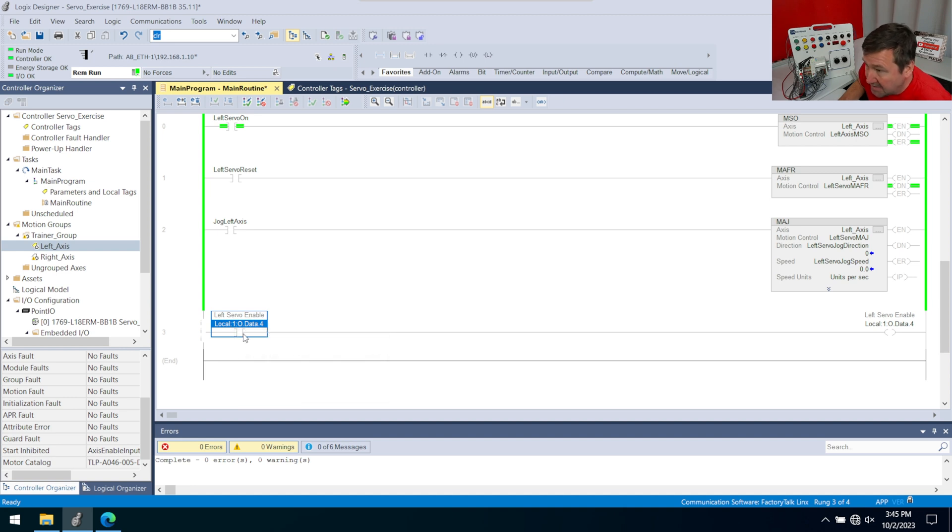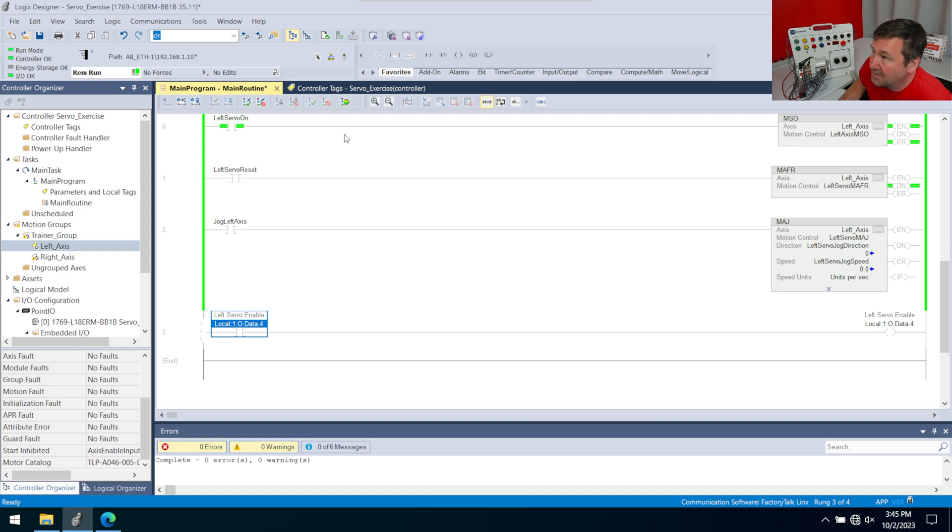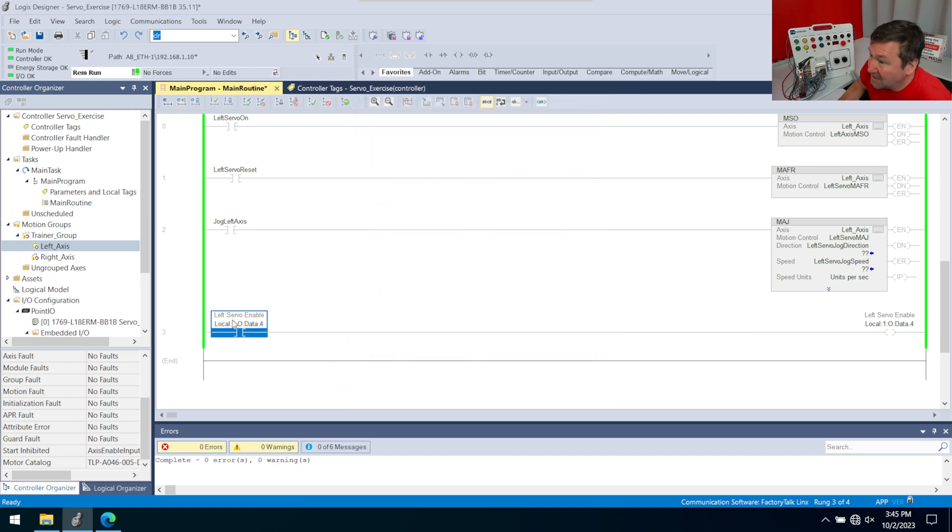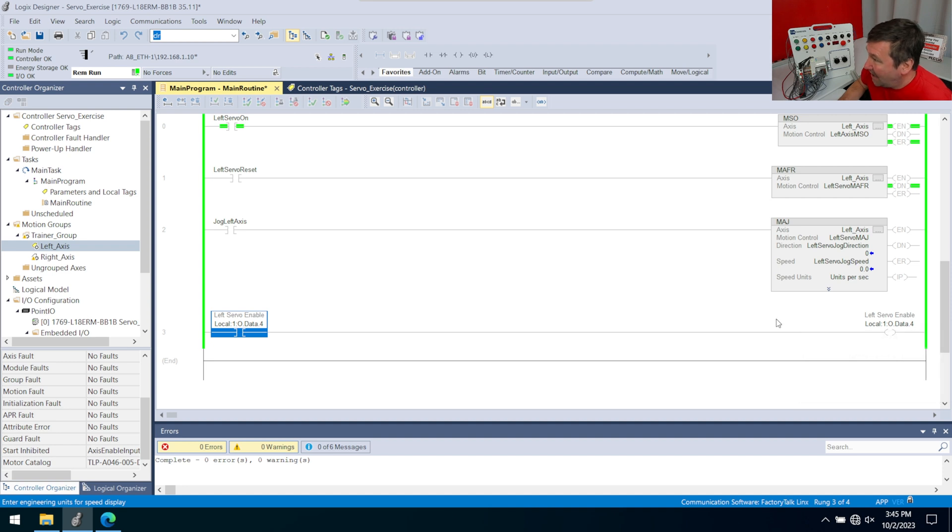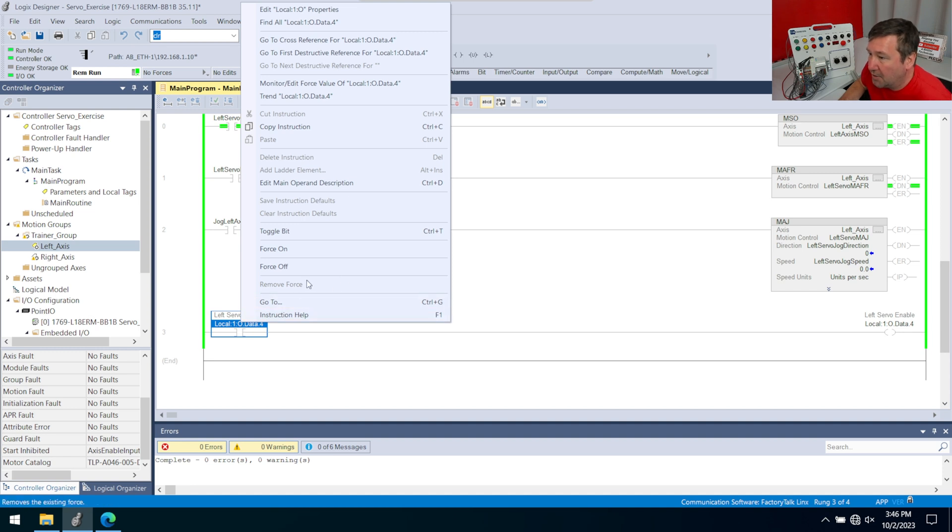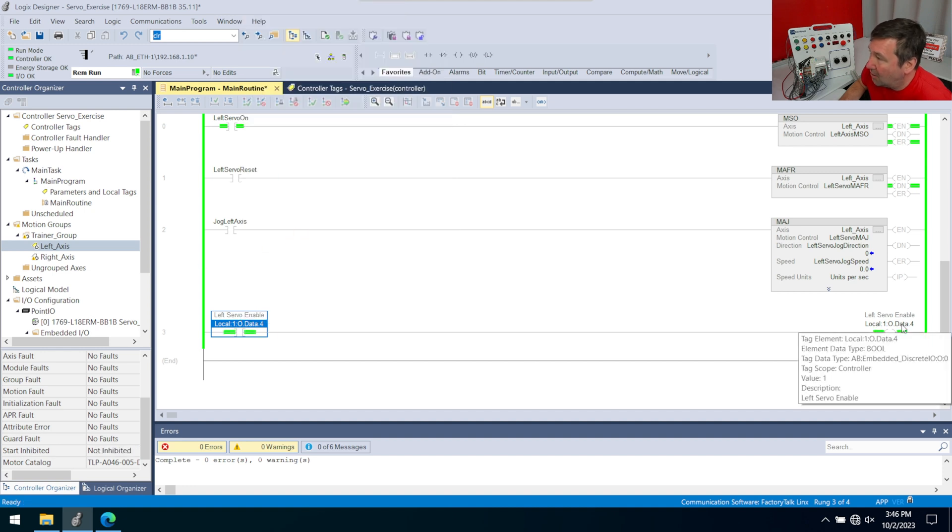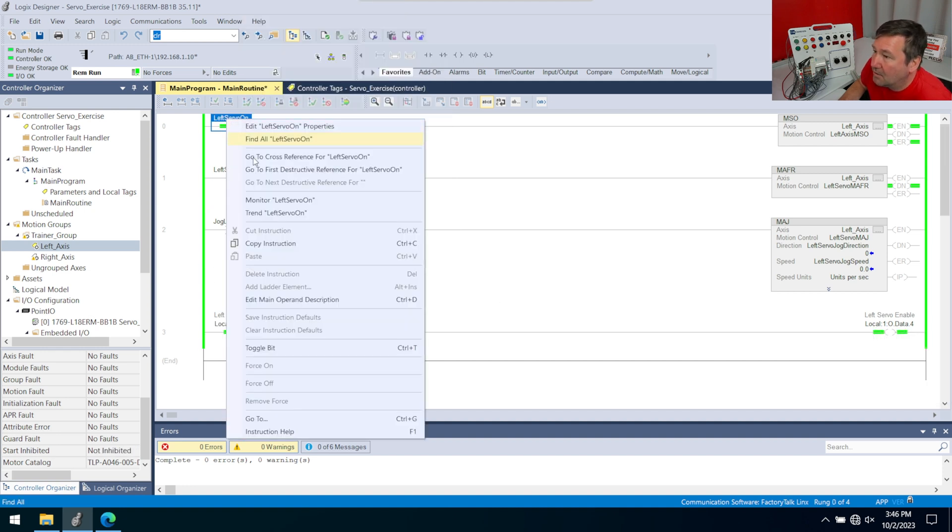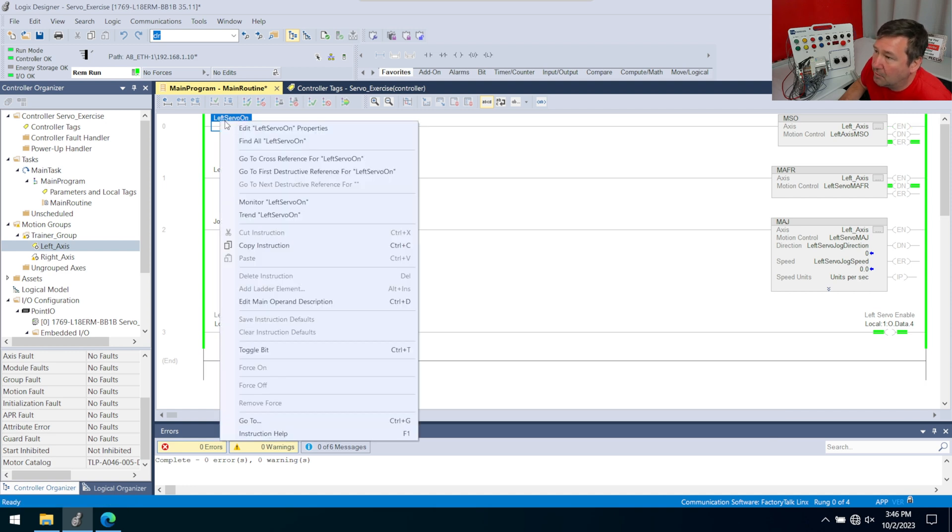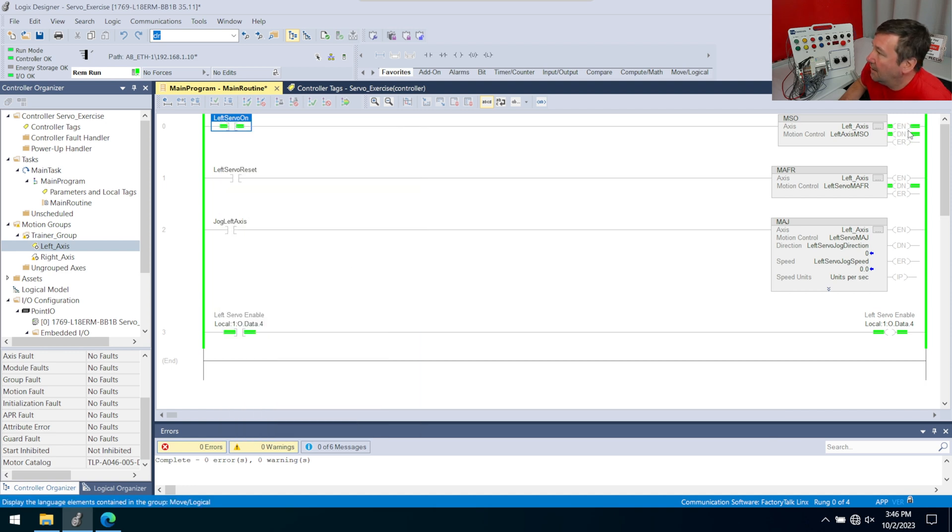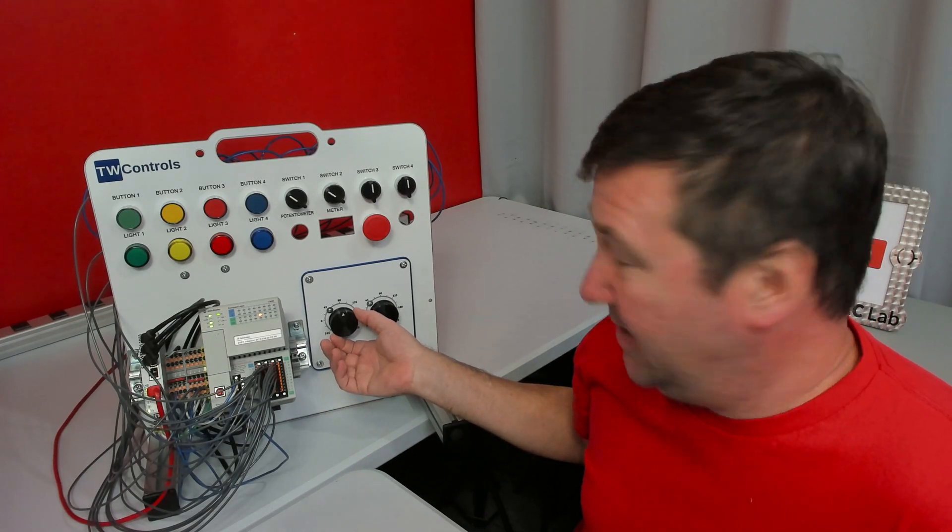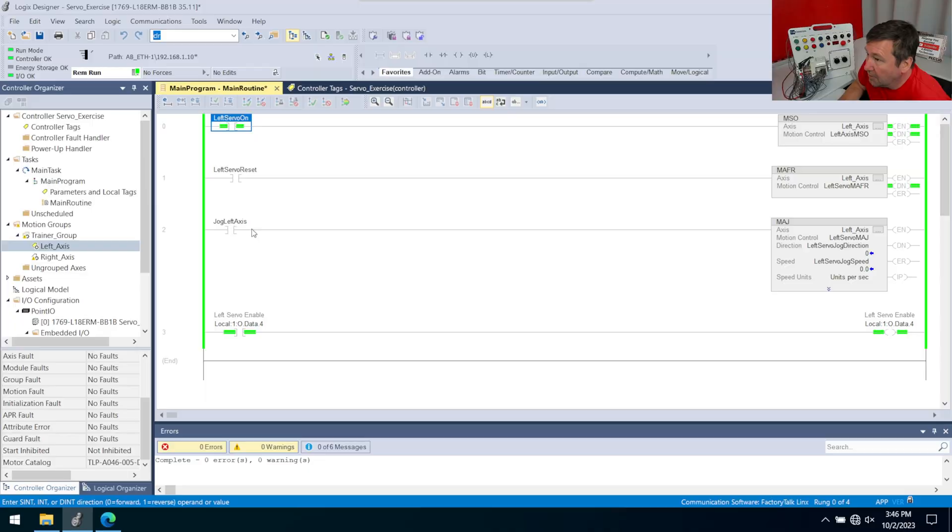Let me show you something we can do to make an easy place to toggle this. We're going to copy that, and I'm just going to bring a new rung down. We're going to put a go look for our one end, and we're going to actually look at local colon one colon O dot data dot four. Then we're going to put an output energize in local colon one colon O dot data dot four. This way, this is looking for a one. If it doesn't have a one, it'll be false and this will go right to zero. If it does have a one, it'll be true and it'll go right to one. So this just gives us an easy place in our program to toggle. I'm just going to right click local colon one colon O dot data dot four, and we're going to toggle the bit. We just want to toggle the bit. That's going to turn on our servo enable. Now we toggle off our MSO, we toggle it right back on, and we look good. If I turn the servo a little bit, I can feel some resistance on it, so I know we're ready to go.